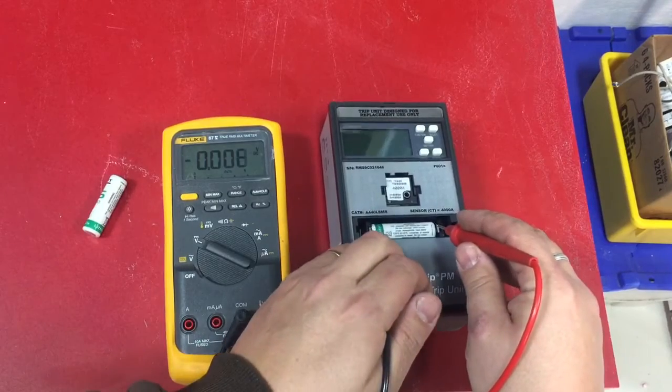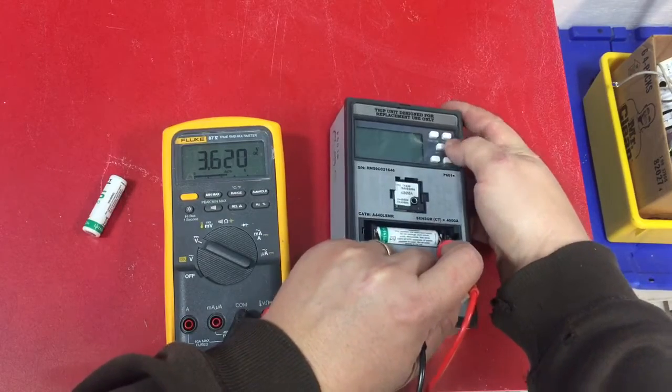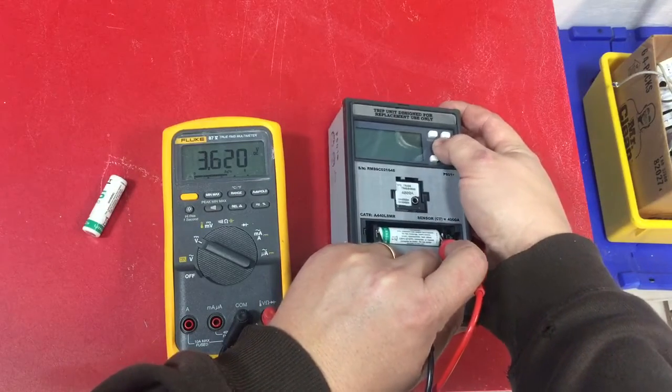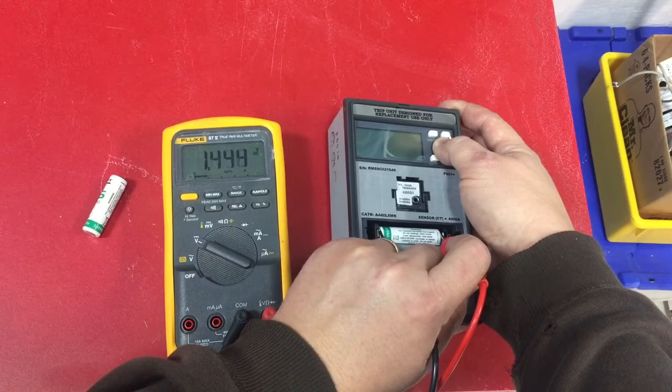Well, the problem with lithium batteries is they're not as simple as just that to test. As soon as you put it under load, put your leads back on there, hit that battery button, watch that voltage drop down to 1.4. It doesn't have enough voltage to be able to power up this trip unit display.